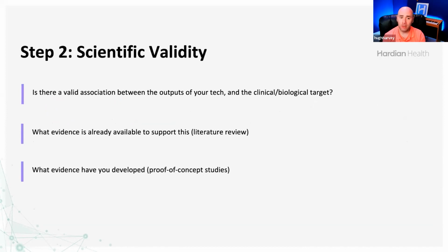In essence, you are asking yourself one question. Is there a valid scientific proven association between the outputs of your device and the clinical thing you're trying to measure? You might already know this in your head, that there is a valid association, but you have to prove that, not only to regulators, but obviously ultimately your customers.